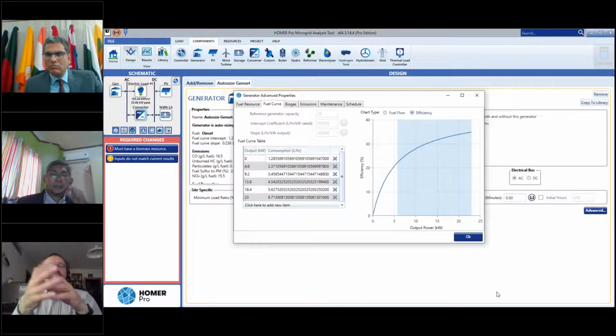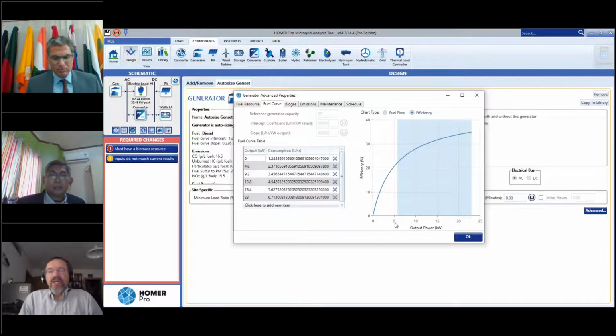So the efficiency really drops off with load, but not only that - there's a maintenance problem with running any kind of generator too low a load. You get condensation in the exhaust stack. There's a whole variety of problems in addition to it just being inefficient. So HOMER enforces a constraint on the minimum load on any kind of generator, gas, diesel, whatever.